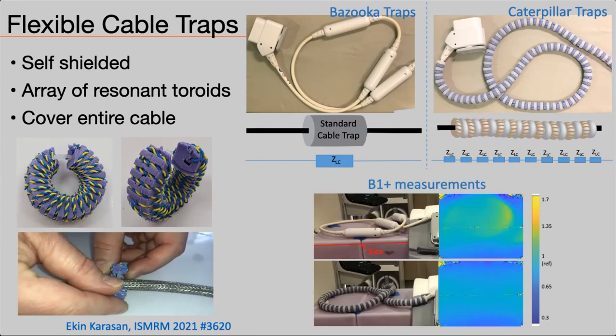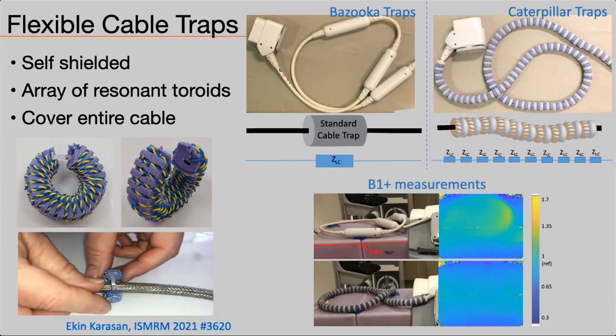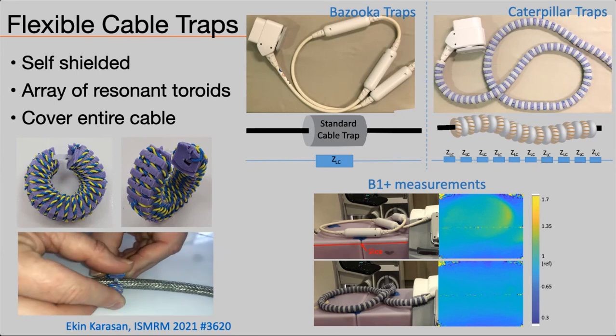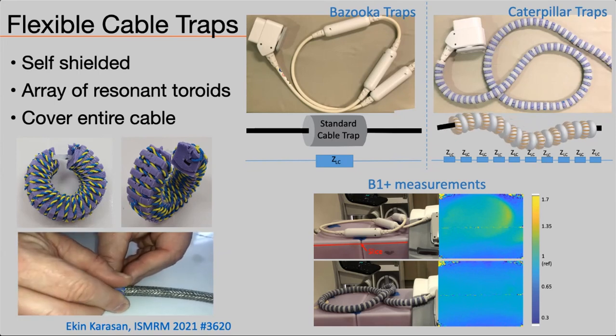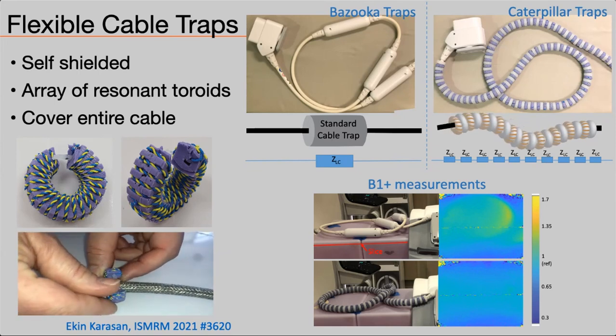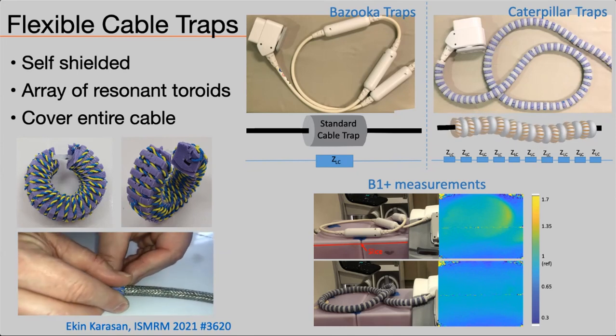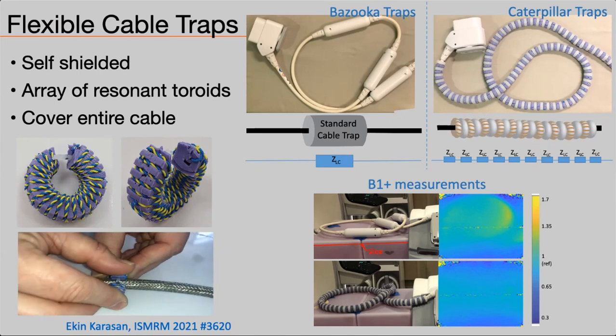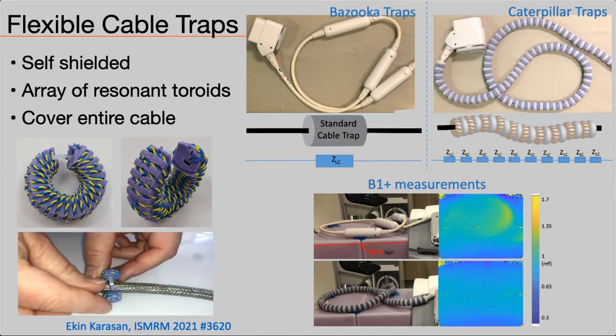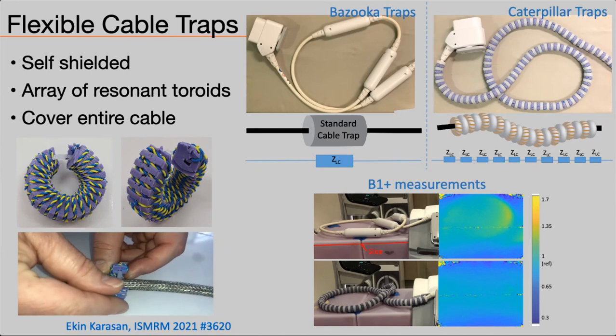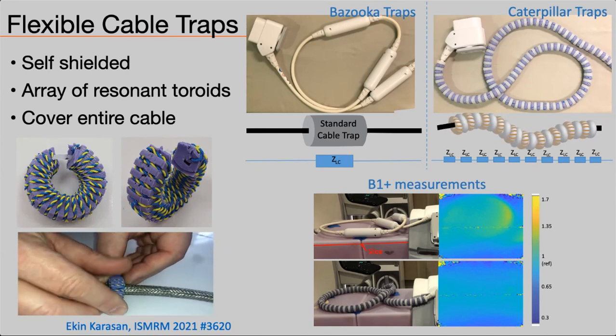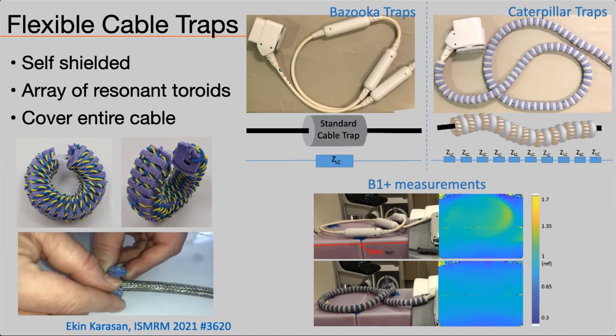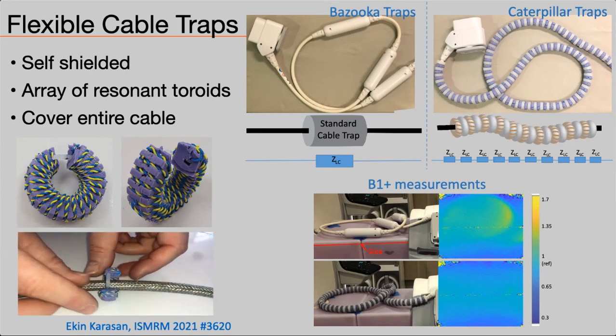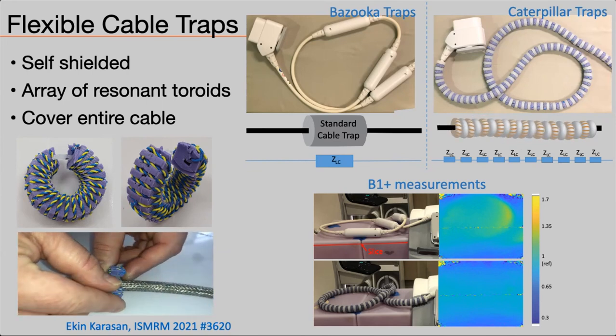In the figure below, you can see a B1 measurement, a B1 transmit measurement experiment in which a B1 map under a winded cable is collected. The system cable exhibits some B1 distortion. So you put the system cable here and you coil it, and now you measure the B1 field in a phantom underneath.